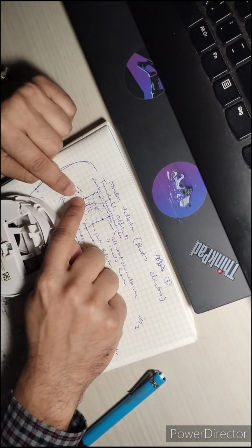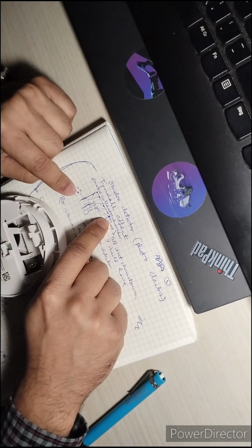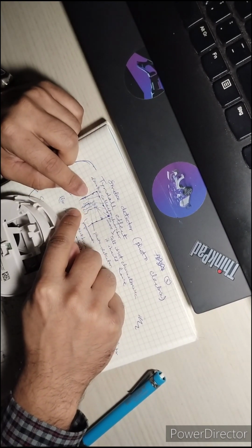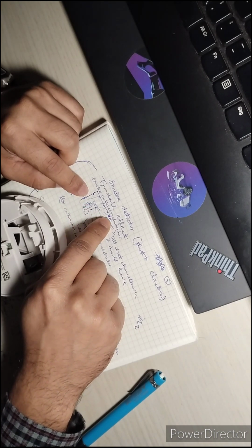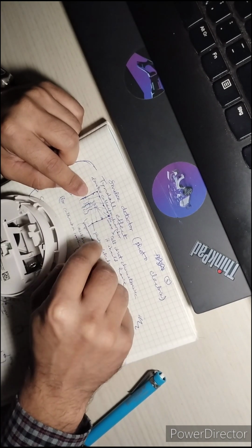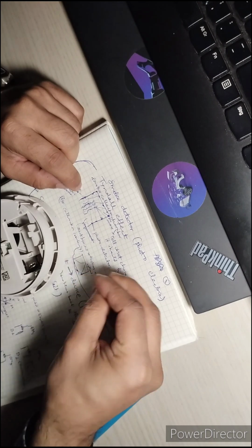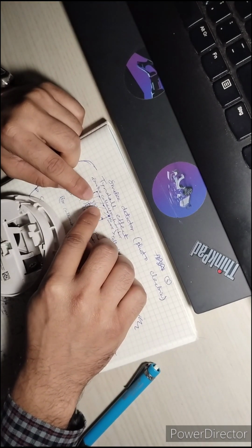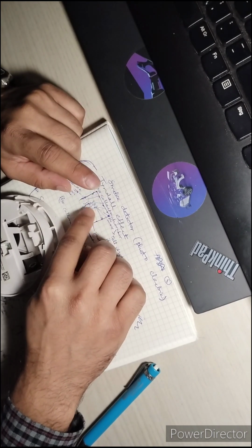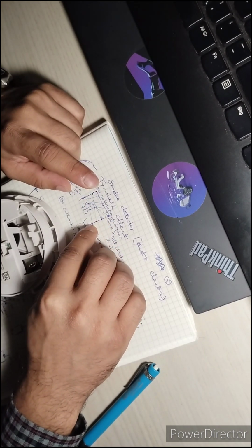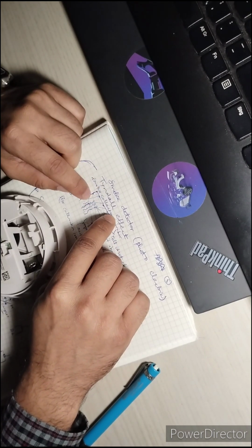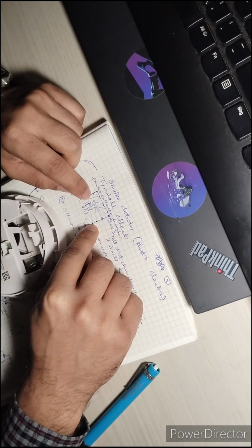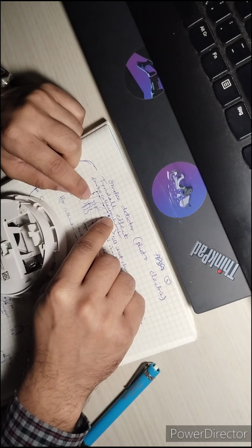And then what happens is that when the light is projected into this controlled chamber where the smoke collects, it has photodetectors, basically light detectors. When there is smoke in the chamber, it scatters this light all around, and the intensity of the light is measured in the form of current when it is detected by these detectors.